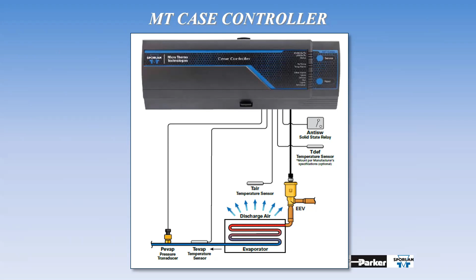Oh, also built in is a solid state relay that will control the heavy duty solid state relay. And this is how we pulse the anti-sweat. So if it's very dry and the anti-sweats only have to be pulsed 10%, we're going to pulse this switch 10%. If it's extremely humid and we need to have the doors active 60 or 70% of the time, we're going to pulse this fast acting switch. So that 70% of the time, or say 7 out of 10 seconds, this switch is going to be active, and we're going to be heating the glass and heating the door frame. And that's all coming right out of the case controller. The other thing with the case controller, it allows you to save money on wiring because you run your input voltage to the case controller, and we're controlling the lights and the fans and everything right out of the case controller. So it cuts wiring costs down. Questions?